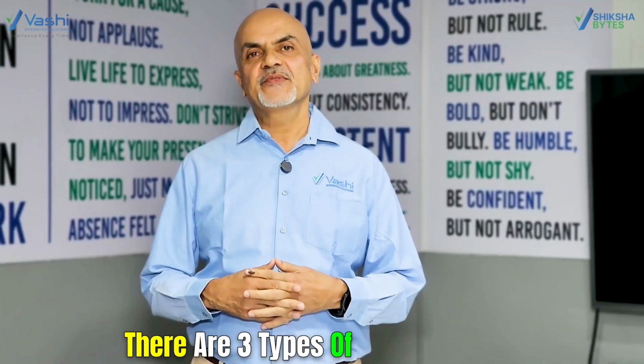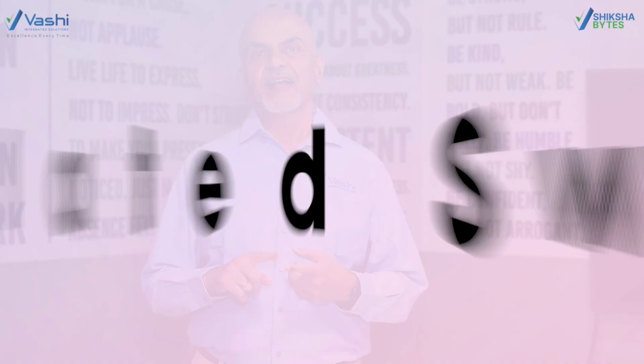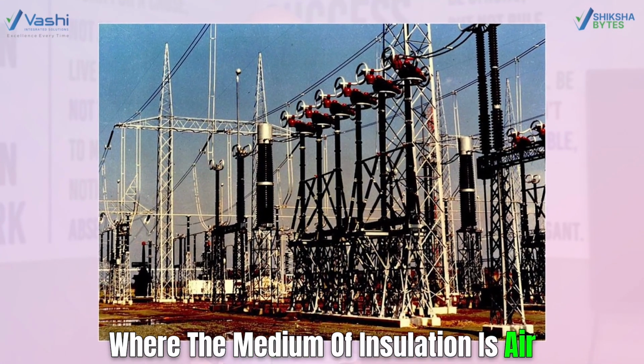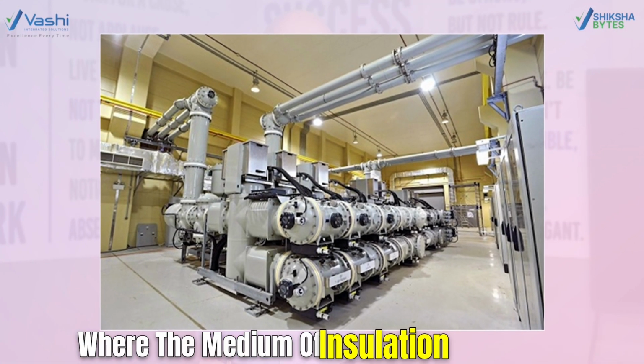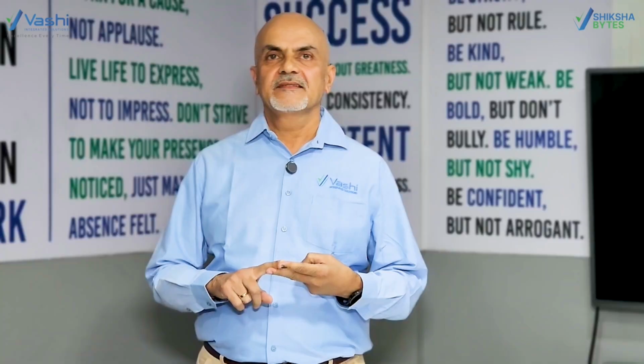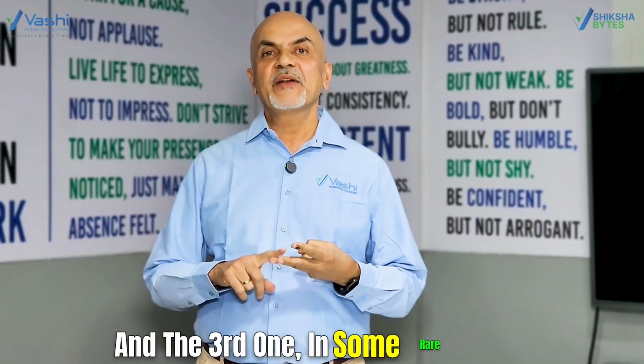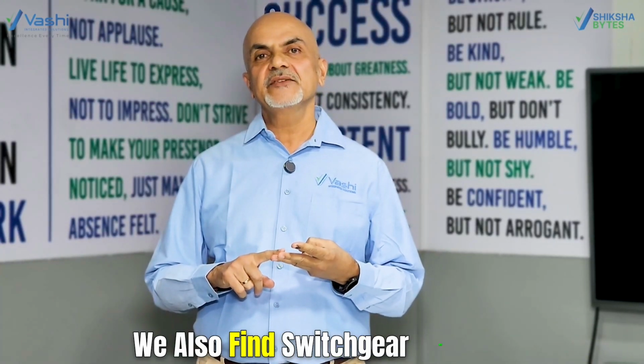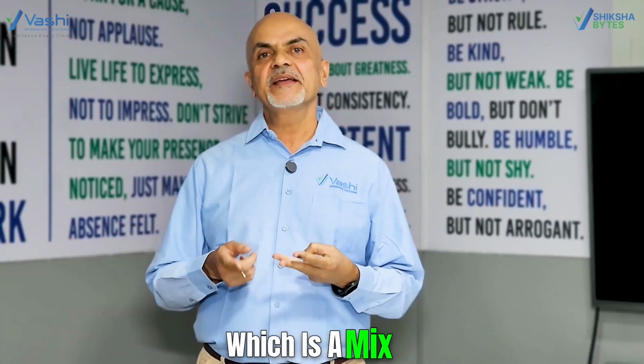There are three types of HV switchgear. The first is air insulated switchgear, where the medium of insulation is air. Second is gas insulated switchgear, where the medium of insulation is SF6 gas. And the third, found in some rare cases, is switchgear with a mixed technology, which is a mix of gas insulated and air insulated.